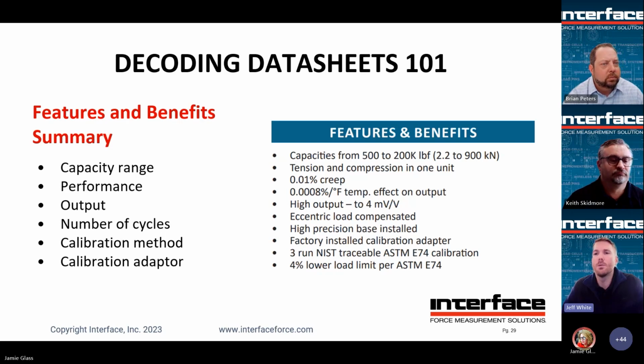Next is output. We offer a 4 millivolt per volt output on many load cells, making it very attractive to some customers, but note that when you get into fatigue applications, the output will be cut in half. Speaking of fatigue, the number of cycles. This is a detail that is sometimes not offered up at the beginning of the search for the best load cell, but it's always important to the success of your measurement. The calibration method, is it going to be tension and compression? Calibration adapter. We offer load cells with integrated cal adapters and therefore able to meet much tighter performance specs.